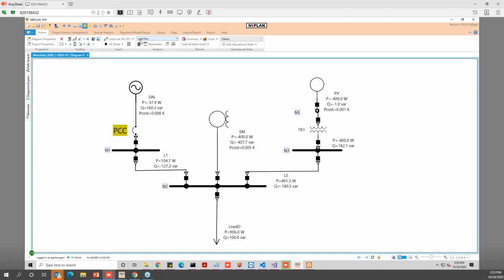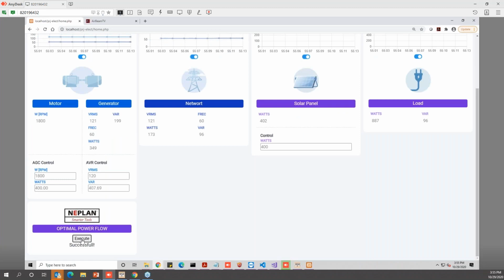Initially I am running here a load flow, and using this load flow, we can implement the set point on the synchronous machine. If we try to keep the set point coming from NEPLAN, we can see how this initial set point is implemented, and we can see the control of the microgrid is according to that set point that NEPLAN has sent. However, that is a load flow.